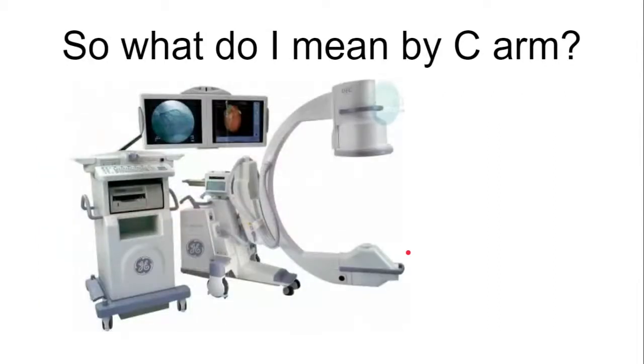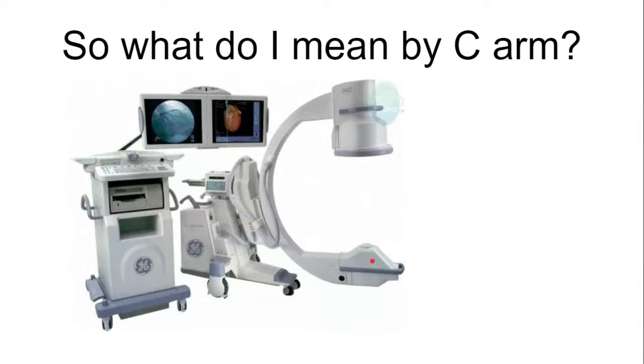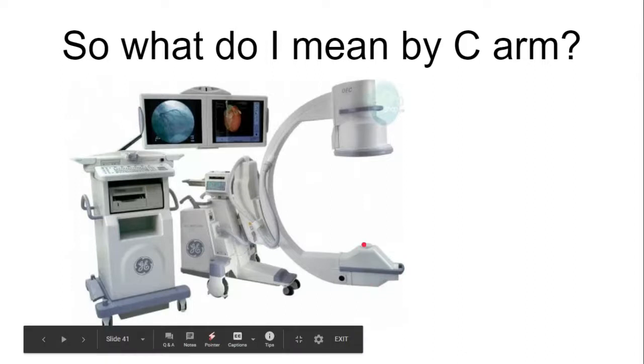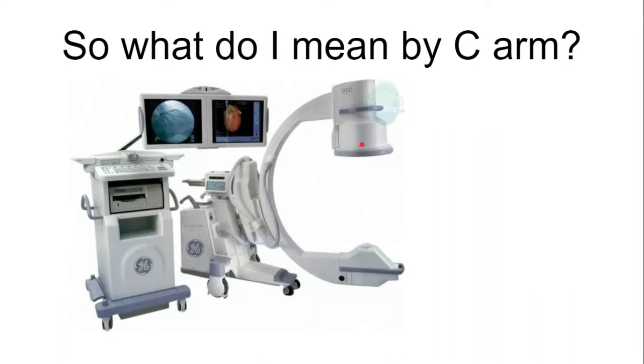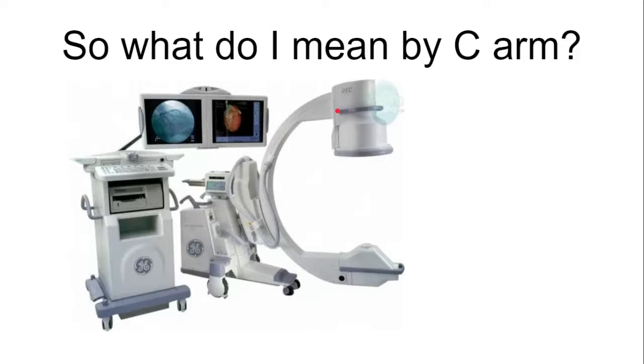Okay, so this is what I'm talking about with the C-arm. Quite simply, the X-ray tube itself is right here. We talked about this before. There is a spacer, as you can see here, that's basically preventing you from putting the patient's skin directly on the X-ray tube, because we know then that the entrance skin exposure would be very, very large and causes burns. The X-ray tube is centered to the image intensifier, which is what you see essentially on the top side. The C-arm here, like we were talking about, has the ability to tilt in all different directions.